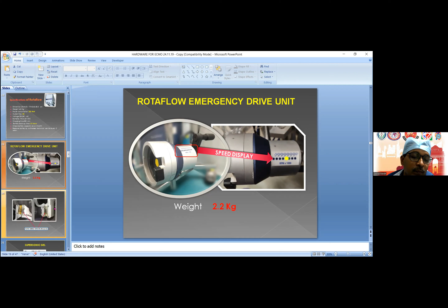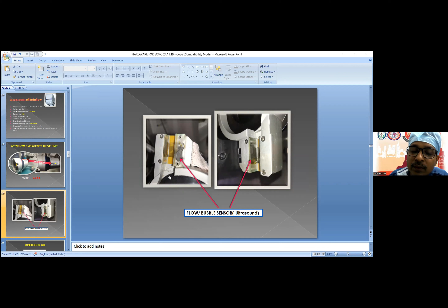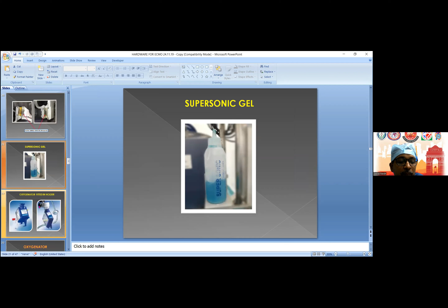The next is where we have set this pump. One wall is generating a signal, and the other wall is receiving the signal. It can identify how much blood is flowing through this path, and if any air passes through this path it can detect it and stop the pump. In between we have to put some gel, as this signal cannot pass through air, so we have to remove the air by placing the gel in the gap between the pump and the wall.